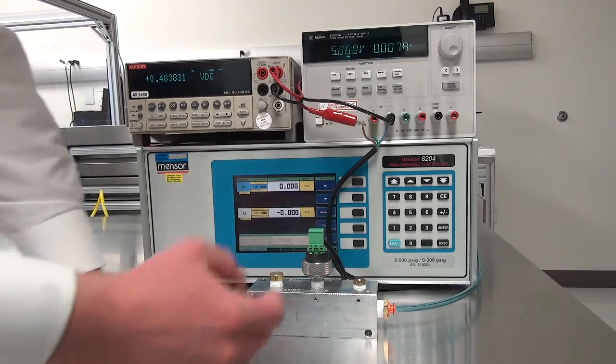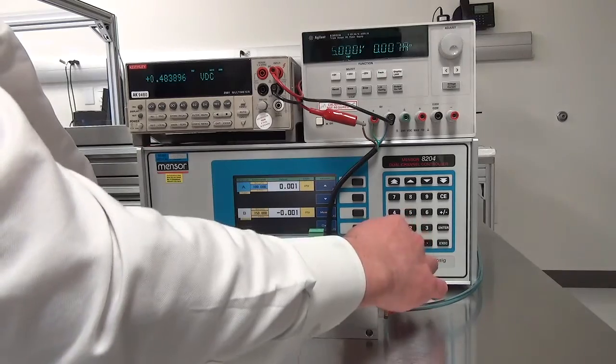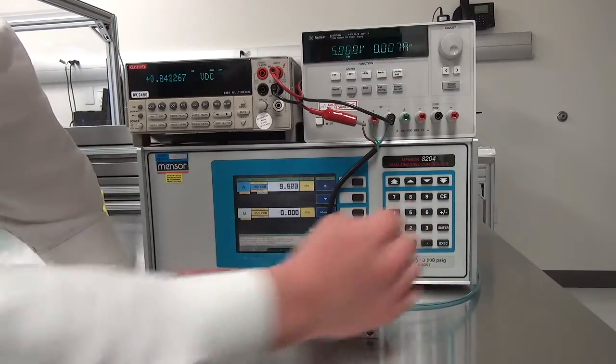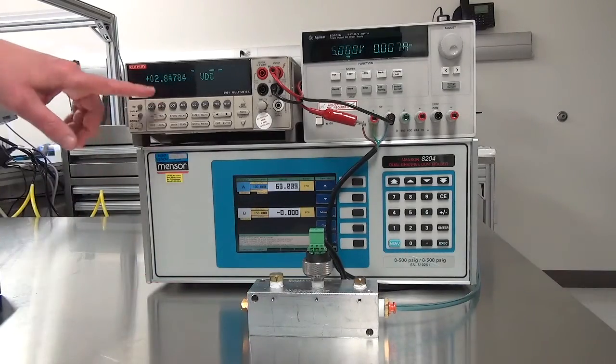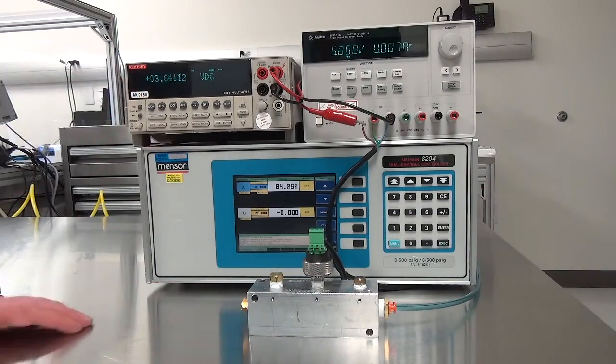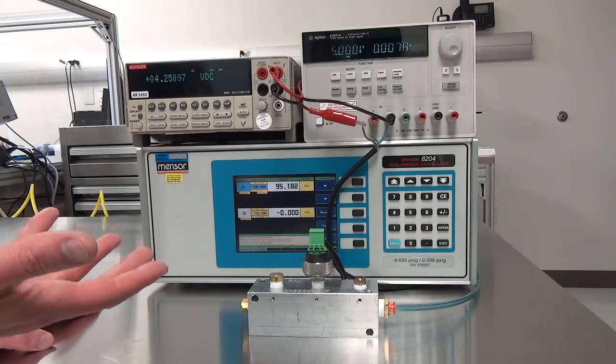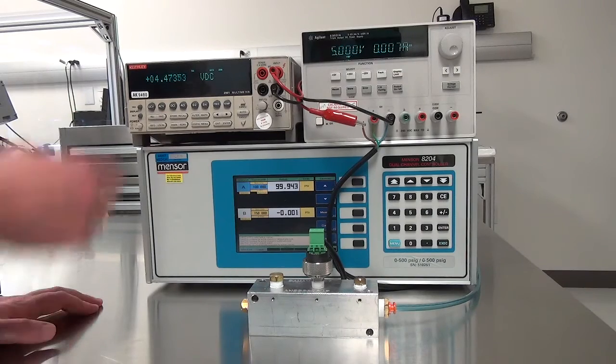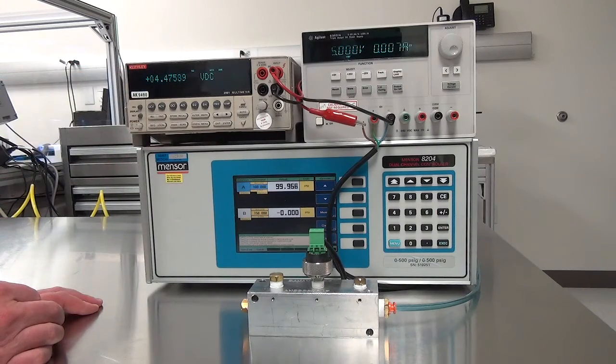Okay and now we're going to apply 100 psi to this 100 psi gauge part. So as it ramps you'll see the output voltage ramping. A 100 psi gauge part should have about 4.5 volts output full scale and here we come to 4.47 volts.